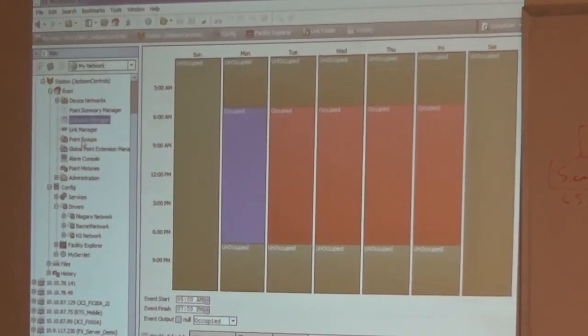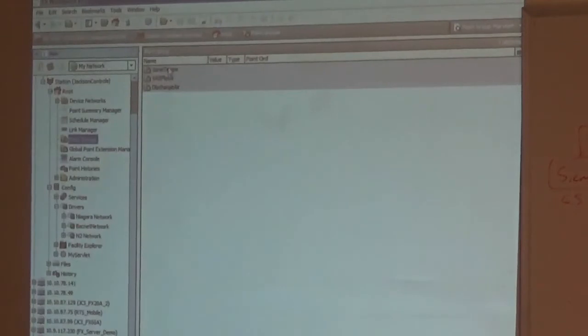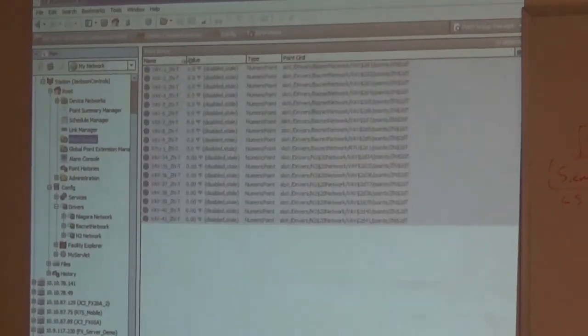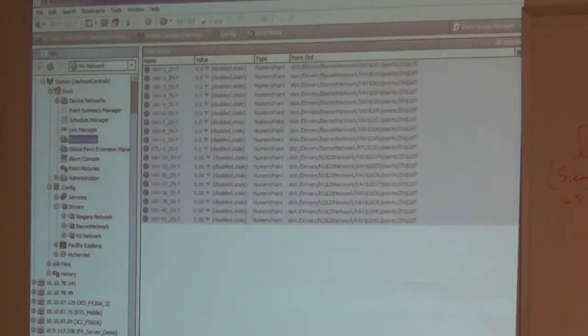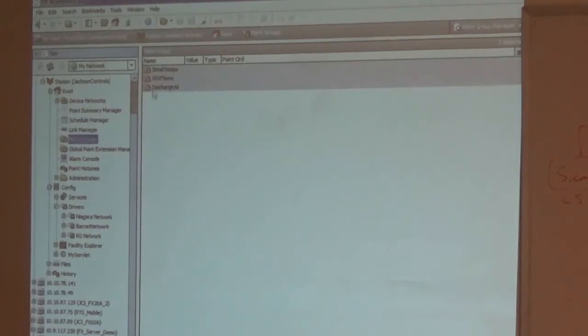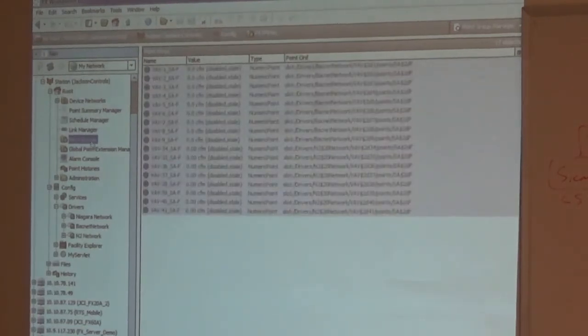Last thing we have here is the little quick thing, point groups. Remember all those point groups we set up? Zone temperatures, VAV flows, and discharge air. If I go in that bucket, all the points that I have that are ZN-Ts, they're all in this bucket and show their values. All the things for VAV flows, they're all going to be there. Everything with discharge air temperature is going to be there.